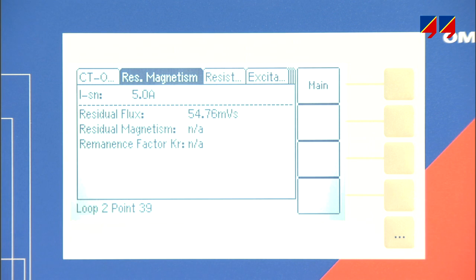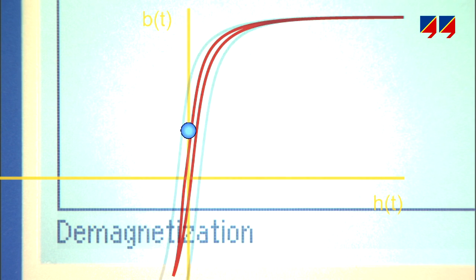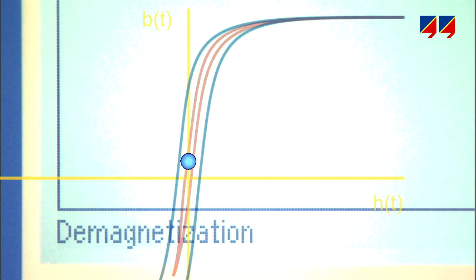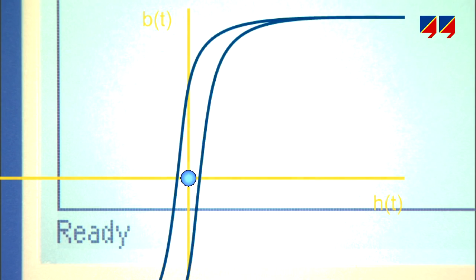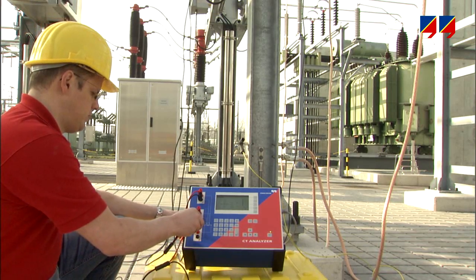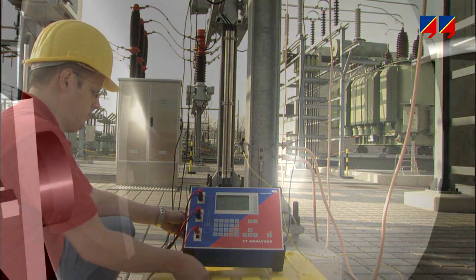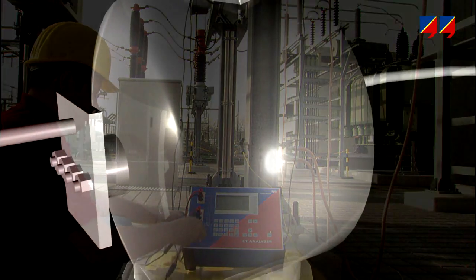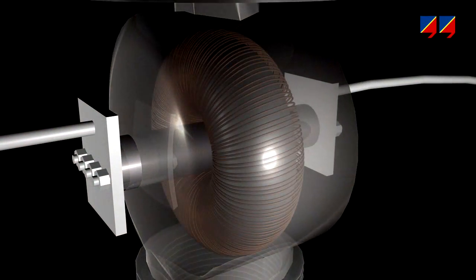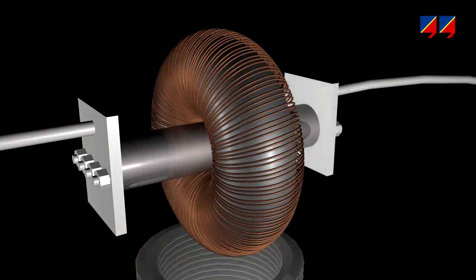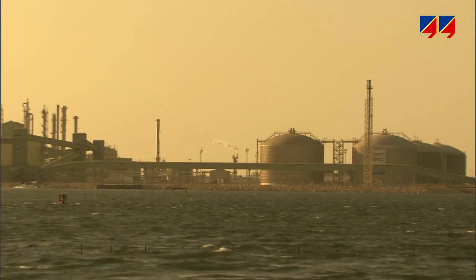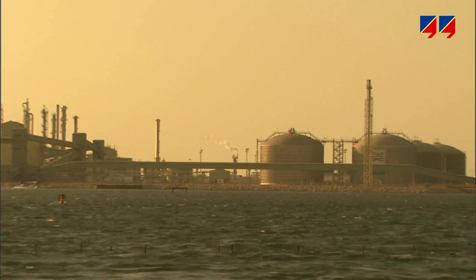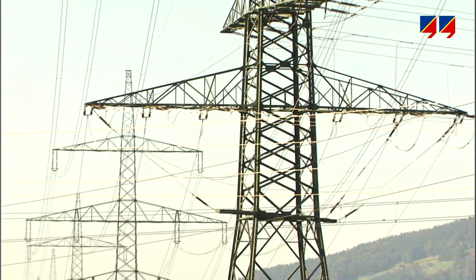After the magnetic remanence is measured, CT analyzer demagnetizes the CT to remove the remanence and return the CT to its optimum operating condition. Besides verifying the typical CT parameters, CT analyzer provides an added insight into the current transformer, assisting protection engineers to ensure a high level of reliability of the power system for existing and future installations.